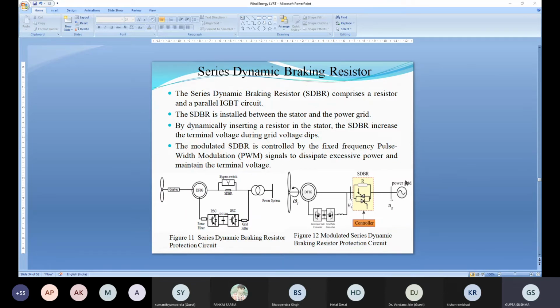Here, if there is a fault in a grid, and during normal operation, firing angle 0 and power flows from DFIG to grid, and this SDBR is out of the picture, it is disconnected.